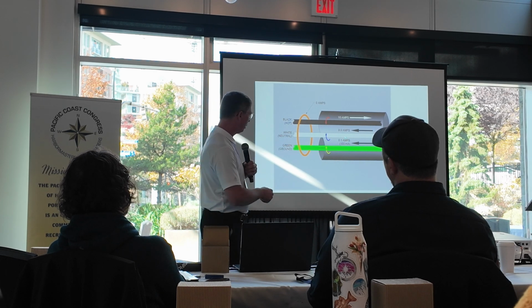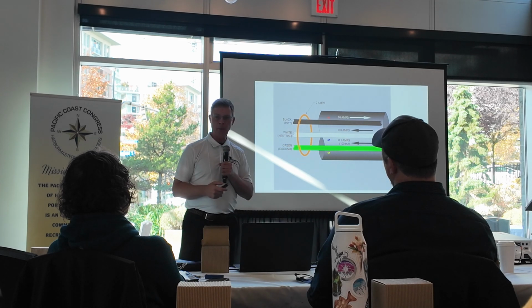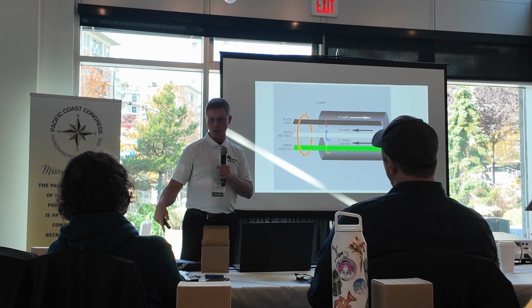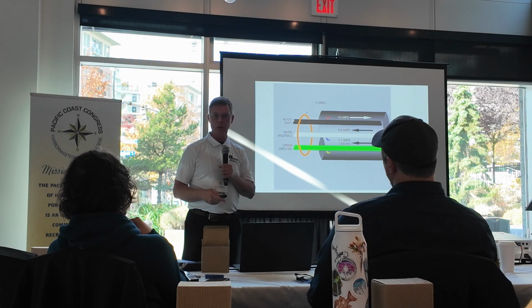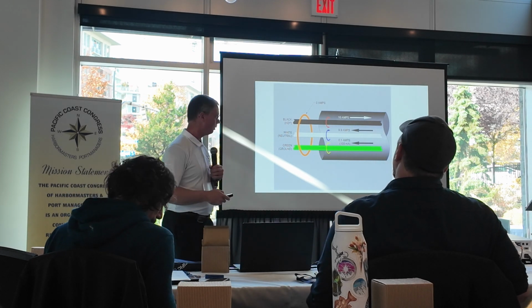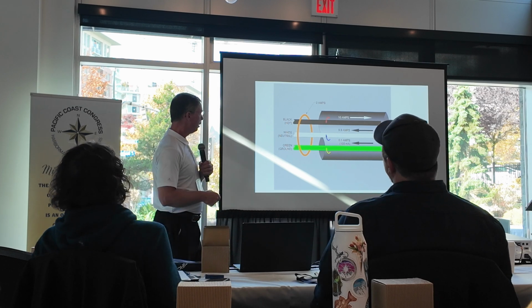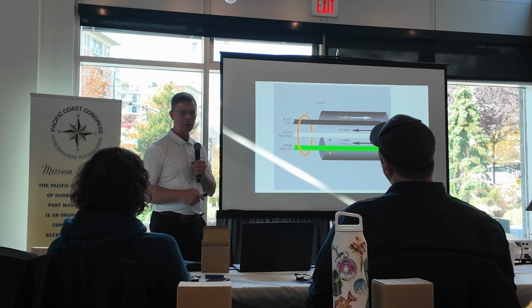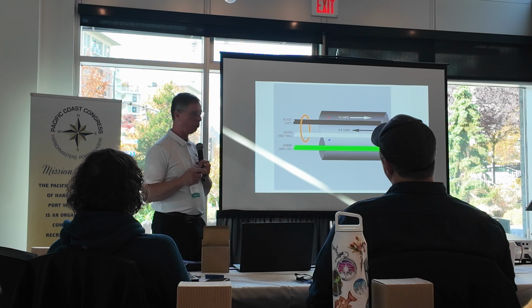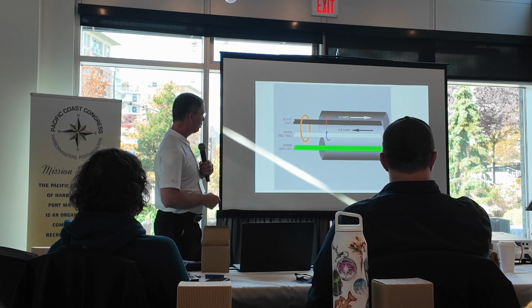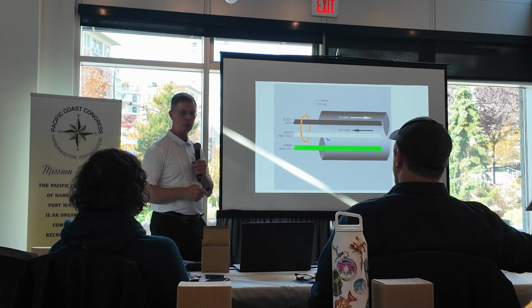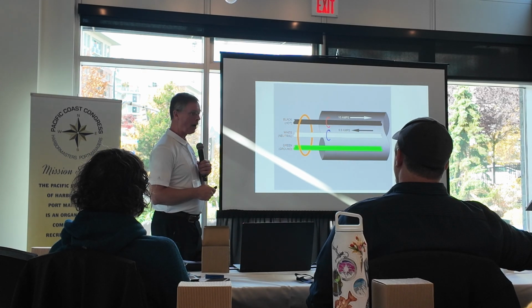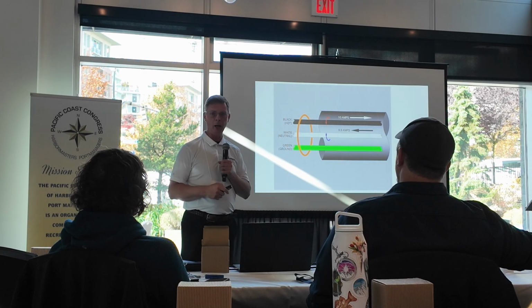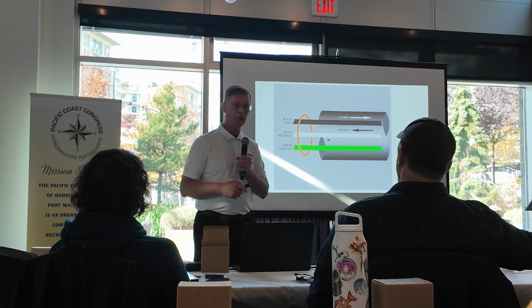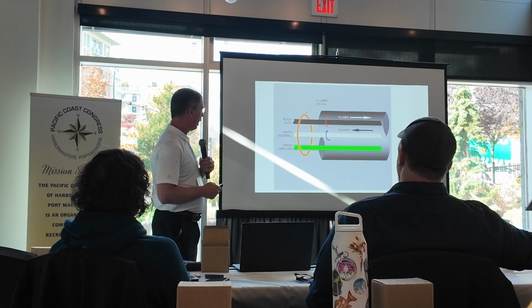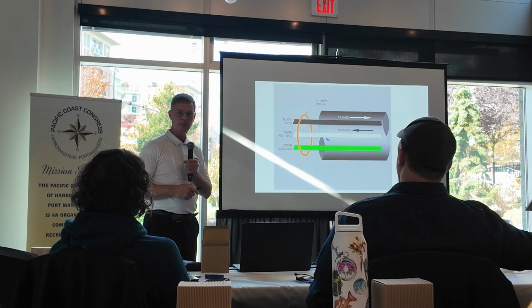It can be, but in this case, that 100 milliamps going through that wire, it's going to go through the path of least resistance and probably not go through you and your shoes or in the water, because it's just not as good a conductor as the copper conductors are. But that's really, really bad. But in this case, let me go through this, where you clamp around the two black and white wires and read that 100 milliamps. But then you clamp around the entire cable, which I do a lot, thousands of times actually, over the last decade, and I read current.